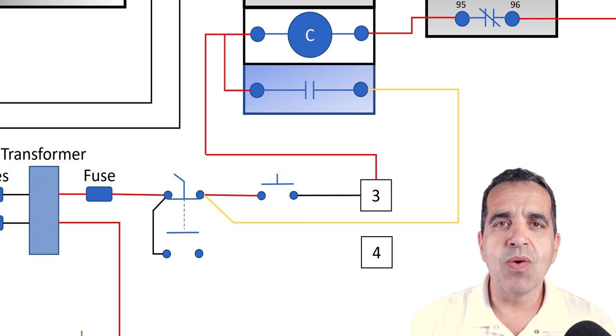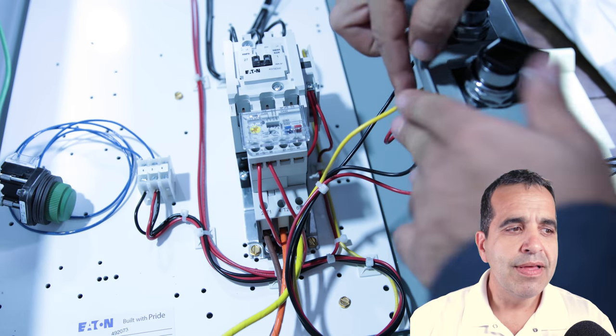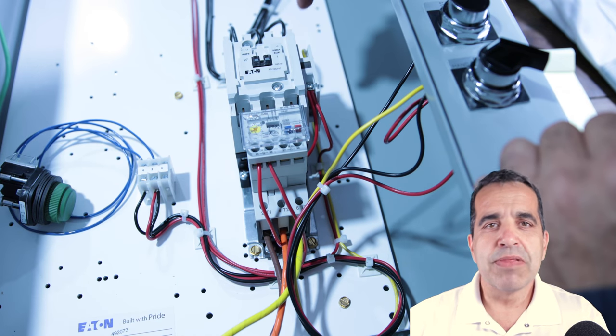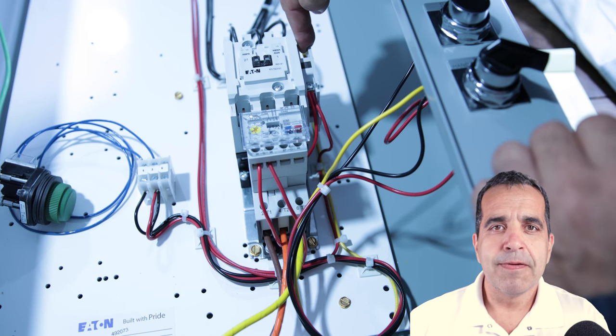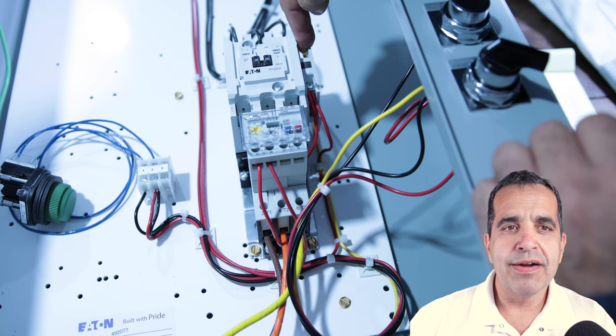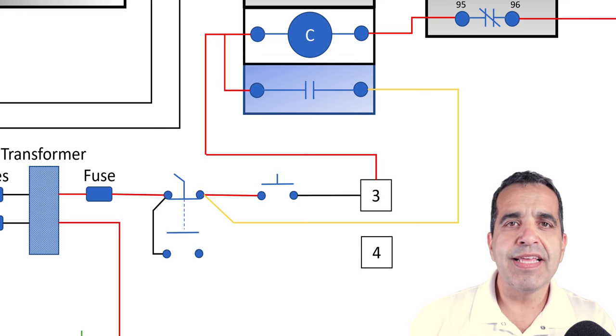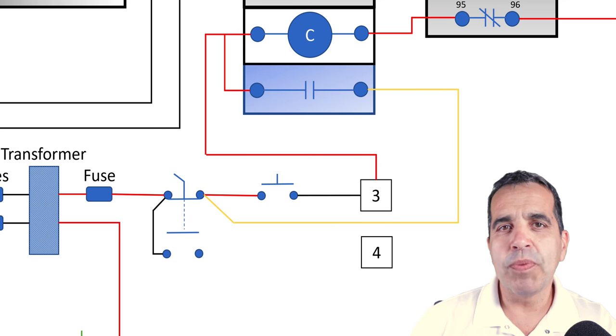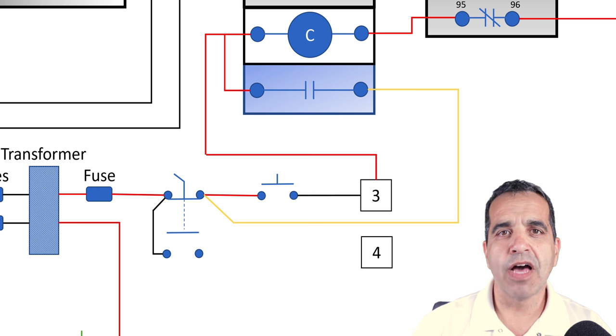The holding contact is a yellow wire going from the supply side to our start button. It's going from that wire over and feeding the other side of our normally open contact on our contactor.